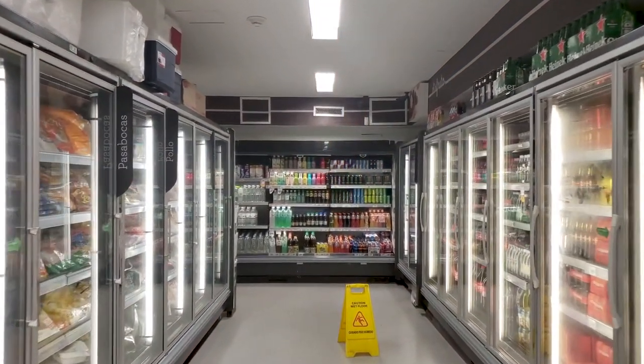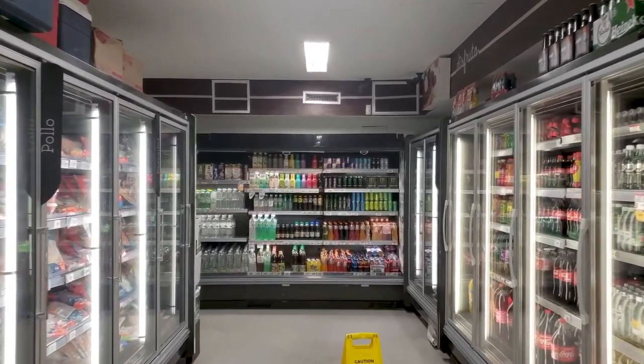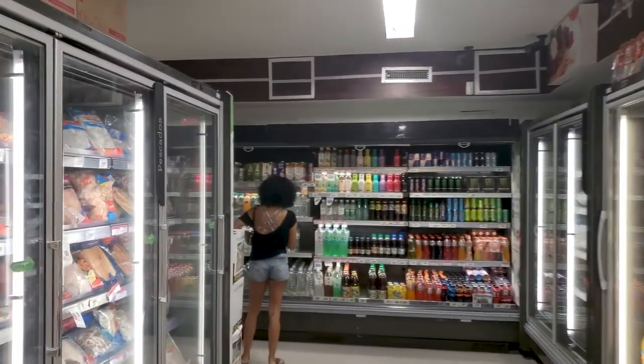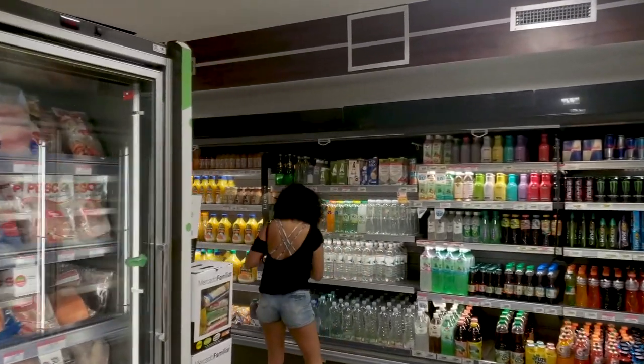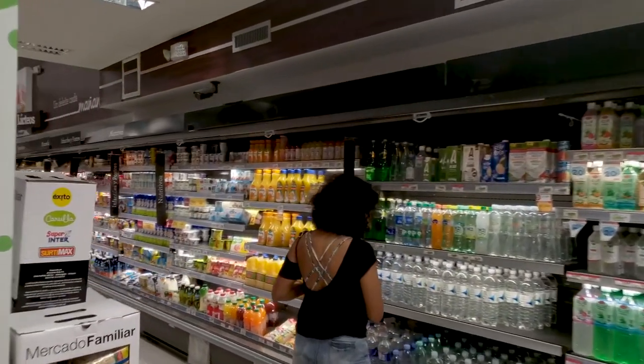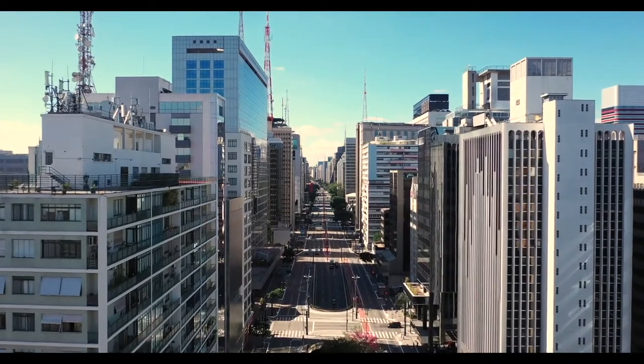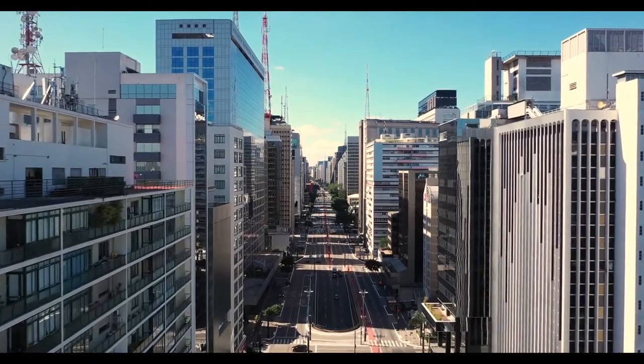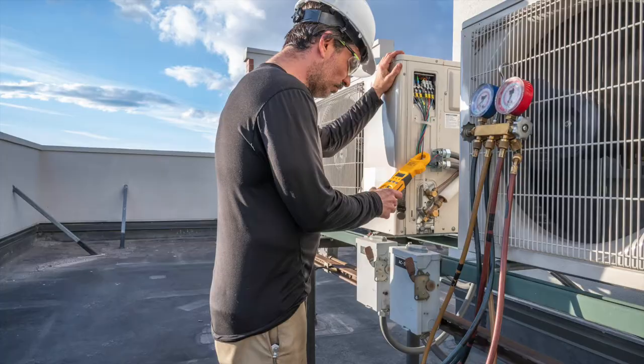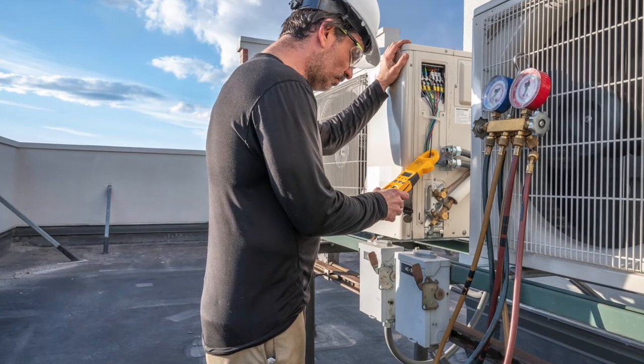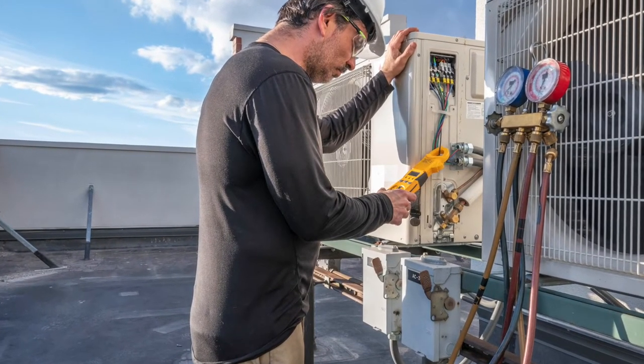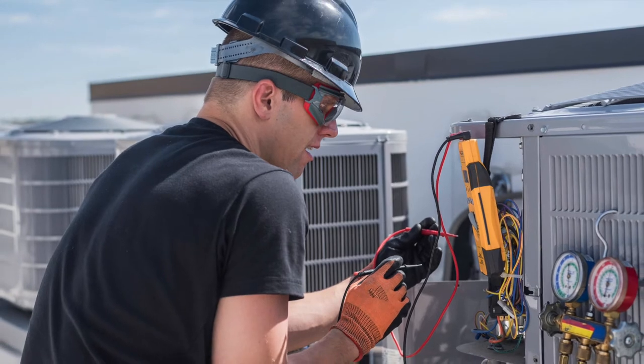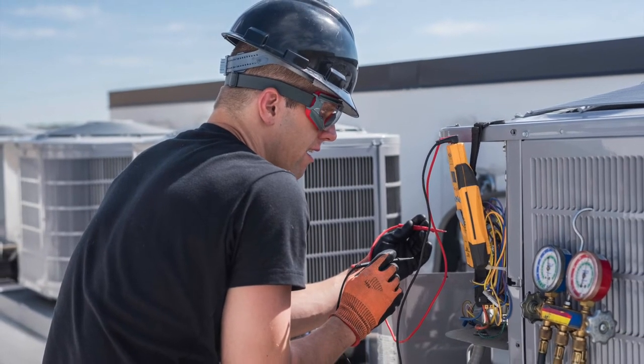Refrigerants are necessary for cooling, some heating systems, and applications like grocery store refrigeration. The key to protecting the environment is to use less refrigerant and to keep it contained in factory-sealed circuits. Refrigerants are changing and will continue to change. New ones are introduced while old ones are phased out. HVAC systems that distribute refrigerant can be rendered obsolete when the refrigerant they use is phased out. It is absolutely not possible to change from a low flammable to a mildly flammable refrigerant. The whole system has to be changed due to design, operation, and control.